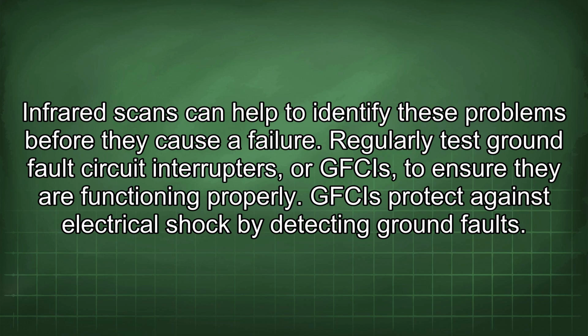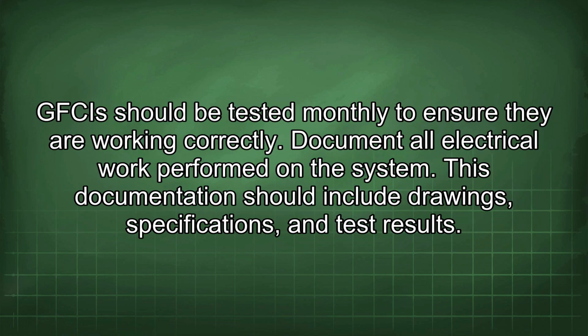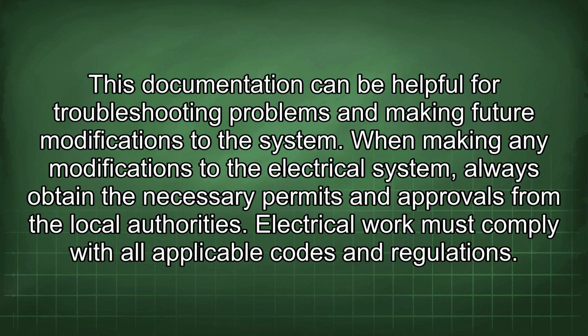Regularly test ground fault circuit interrupters, or GFCIs, to ensure they are functioning properly. GFCIs protect against electrical shock by detecting ground faults. GFCIs should be tested monthly to ensure they are working correctly. Document all electrical work performed on the system. This documentation should include drawings, specifications, and test results. This documentation can be helpful for troubleshooting problems and making future modifications to the system.